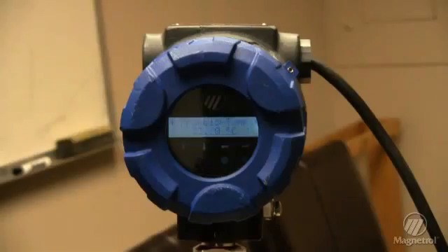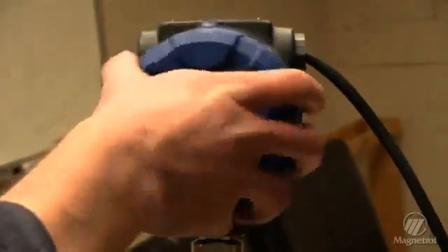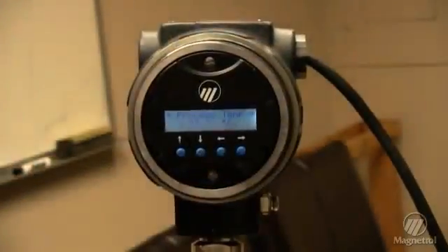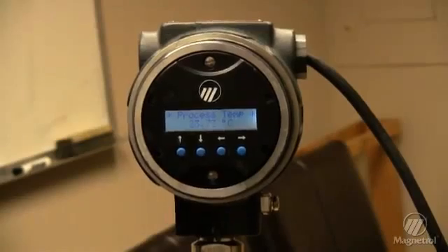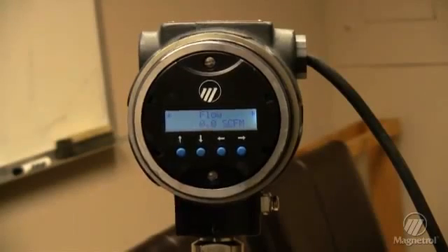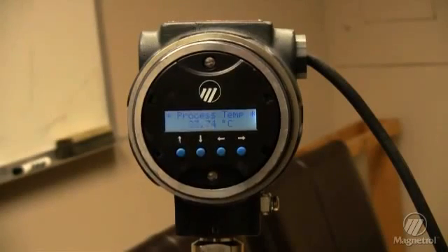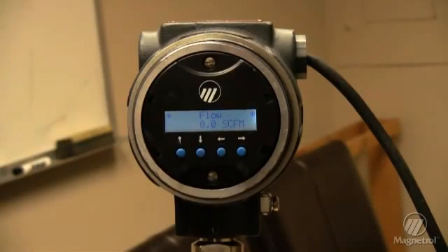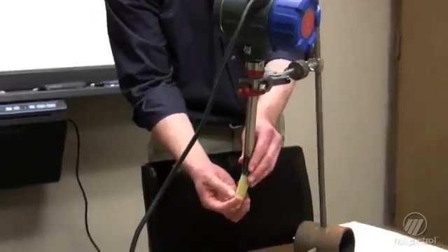The first test is a low flow validation. During the test, the heater power is set and the temperature difference between the RTDs is measured. To do this, wrap the sensor tip so no airflow can flow past the pins.